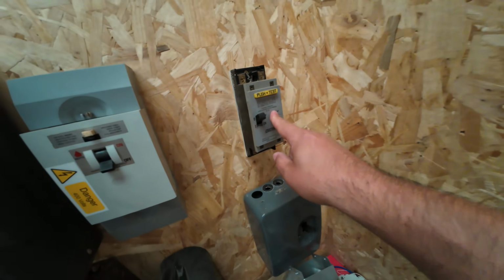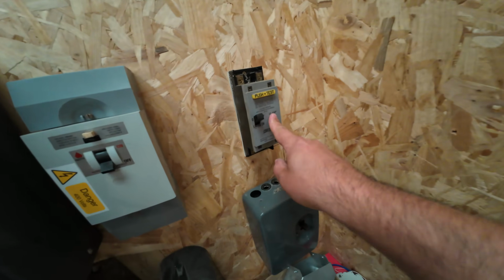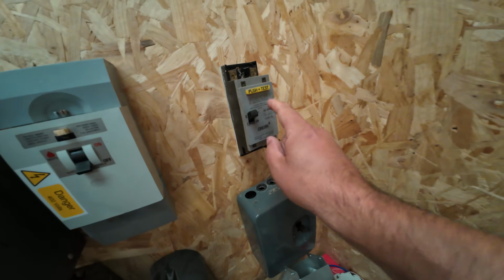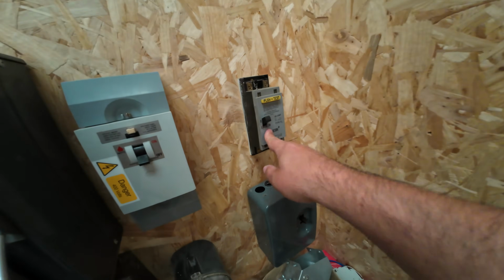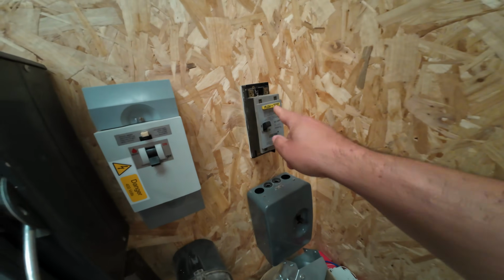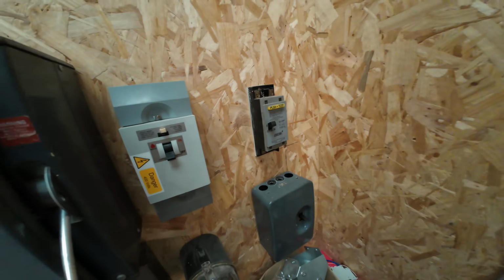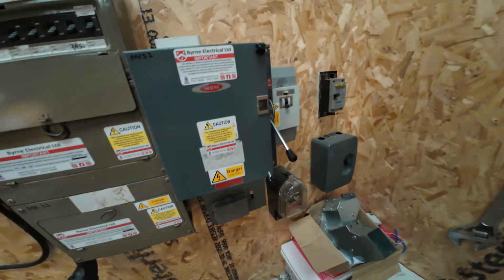So these are voltage operated earth leakage circuit breakers, and these are BS842. You typically find those off the main service head on an old TT installation, and a lot of them no longer work, but they just sit there as an isolation point because no one's ever gone to the trouble of removing them.